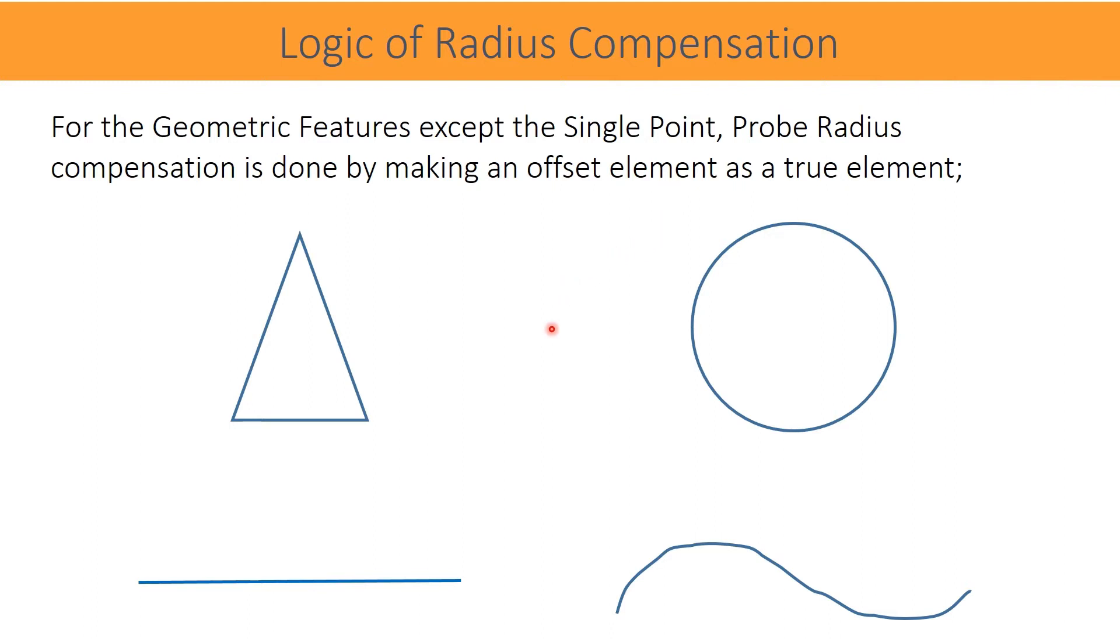This is a straight surface. For an example, let us discuss. Points are measured with the stylus. Software passes a feature through all the centers. After construction of the feature, it is offset by a probe stylus radius value. This is the easiest method of radius correction by offsetting a complete feature.